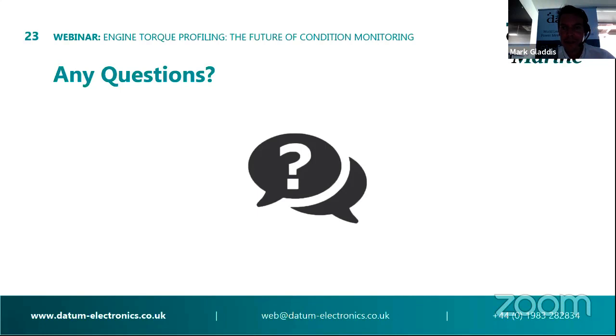The nice thing with our system is that directly from the strain gauge, we digitize the signal before it goes to the amplifier. Unlike many other systems on the market that have analog circuitry at the front end, everything we do from the strain gauge onwards is digitized, meaning it's not susceptible to changes in temperature in the engine room. So we don't suffer drift with our systems. The day it's installed, it's calibrated and zeroed, and that's it for the life of the system. The calibration itself is theoretical, and as long as there are no physical changes to the shaft, we use certain constants based on the gauge factor, Poisson's ratio, Young's modulus, and the shaft diameter. So unless the physical shaft changes, there's no need to recalibrate. The day it's installed, we zero it, calibrate it, and that's there for the life of the system, normally for the life of the vessel and beyond.